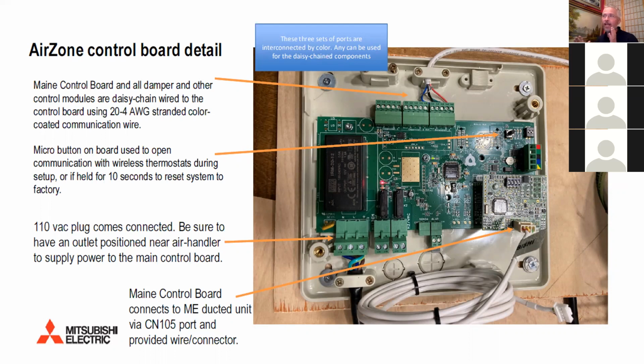AirZone, if you're using motorized dampers, you cannot use an electric heat kit. It doesn't have sensors to ensure that there's sufficient airflow to prevent a total meltdown. So you cannot use an electric heat kit with AirZone dampers.